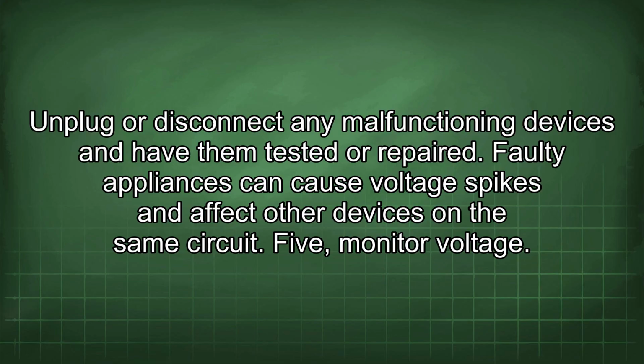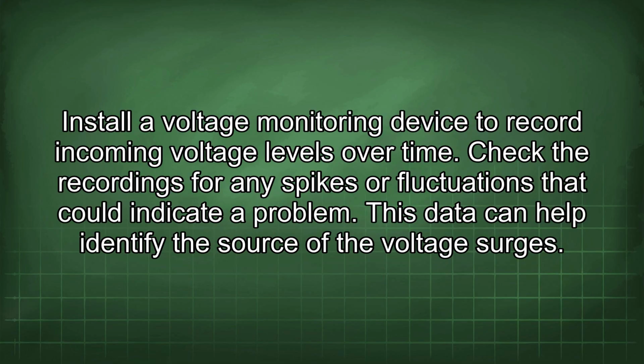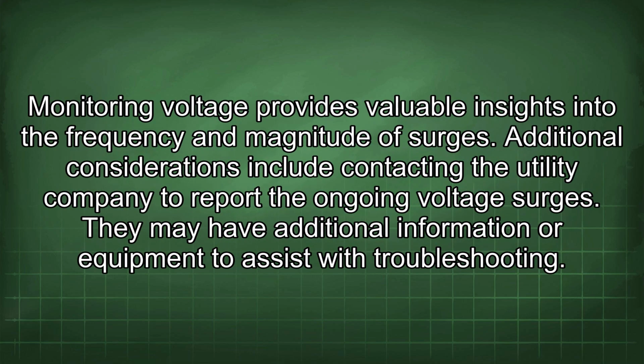5. Monitor voltage. Install a voltage monitoring device to record incoming voltage levels over time. Check the recordings for any spikes or fluctuations that could indicate a problem. This data can help identify the source of the voltage surges. Monitoring voltage provides valuable insights into the frequency and magnitude of surges.